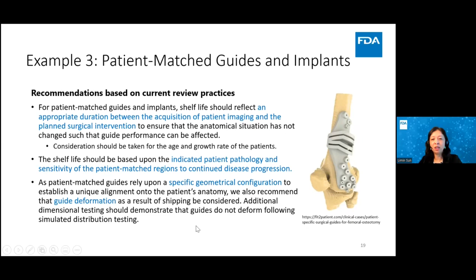Also, all patient-matched guides rely upon a specific geometrical configuration to establish a unique alignment onto the patient's anatomy. We also recommend that guide deformation as a result of shipping be considered, and additional dimensional testing should demonstrate that guides do not deform following simulated distribution testing. As I said, product shelf life testing is device specific. So for any other device, we would recommend you check with the OHT office that regulates the specific device for relevant guidance documents or standards.